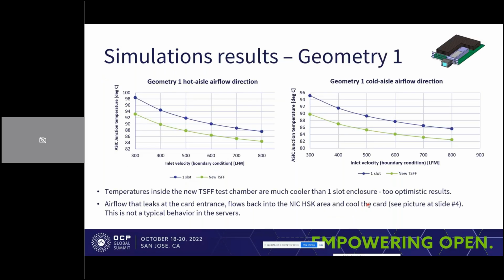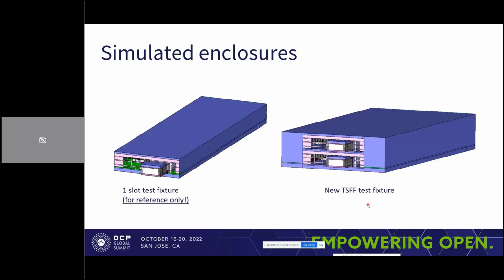Here you can see the results and comparison between the one-slot test chamber and the new TSFF slot chamber. The problem that I see here from my side is a significant difference in the temperatures between these two chambers, and the new TSFF test chamber is significantly cooler, has significantly lower temperatures for the ASIC. So I'm afraid that this result we see in this simulation is just too optimistic, and it happened because of this airflow behavior that you can see here.